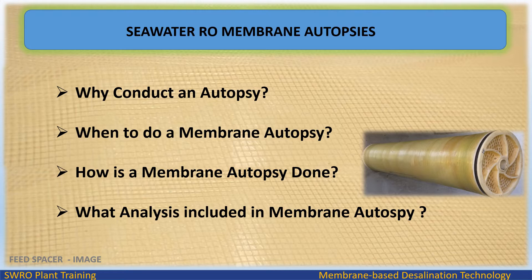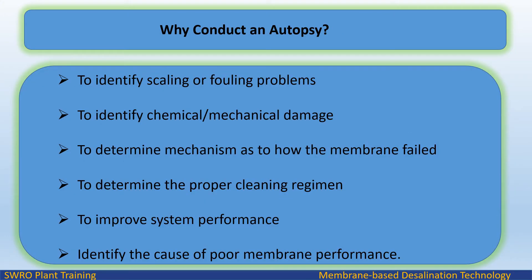Why conduct an autopsy? A membrane autopsy is performed to identify scaling or fouling problems, to identify chemical and mechanical damage, to determine the mechanism of membrane failure, to determine the proper cleaning regimen, to improve system performance, and to identify the cause of poor membrane performance.